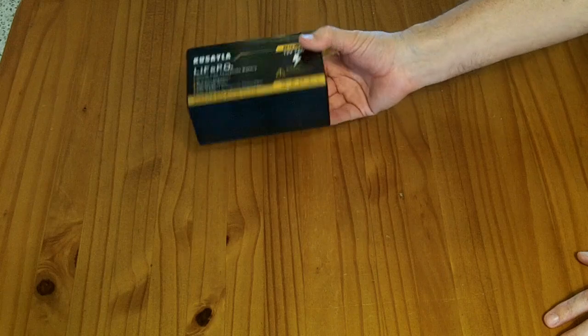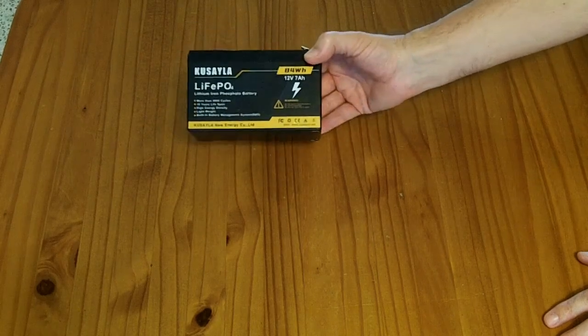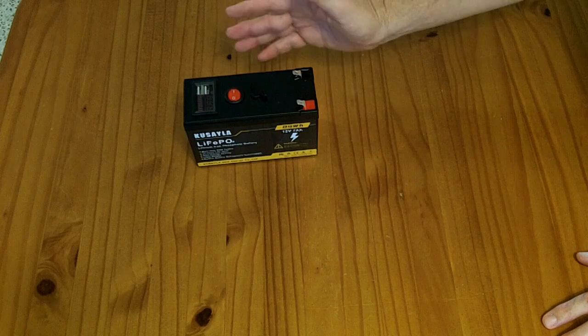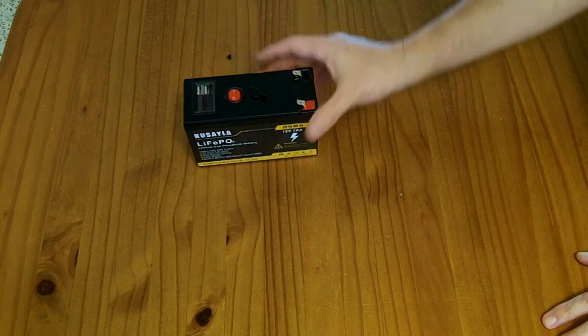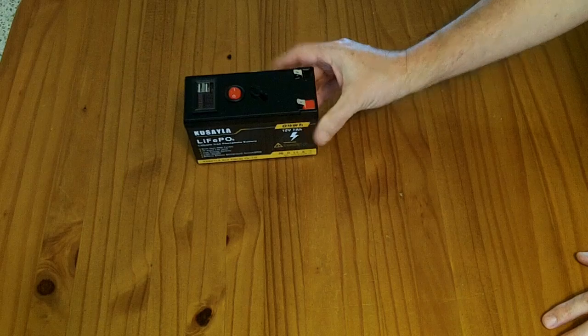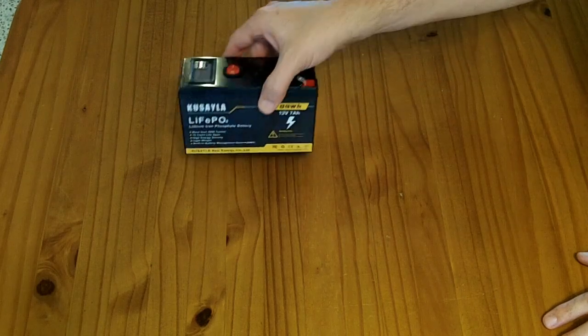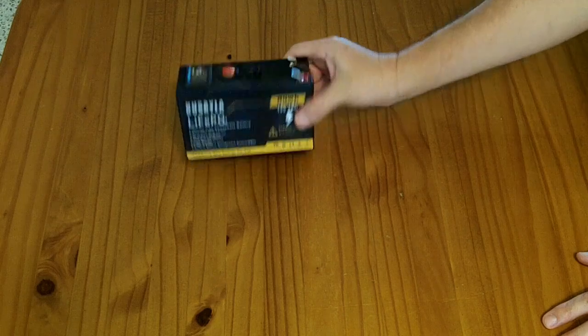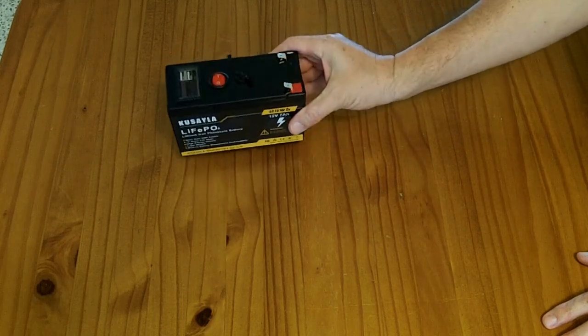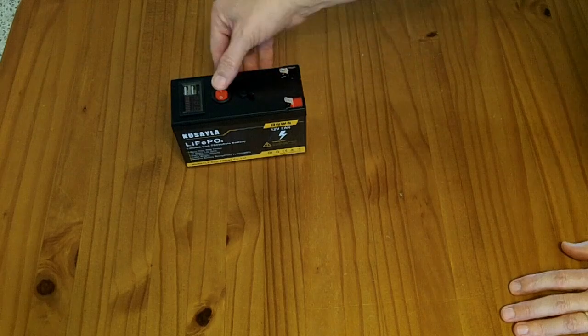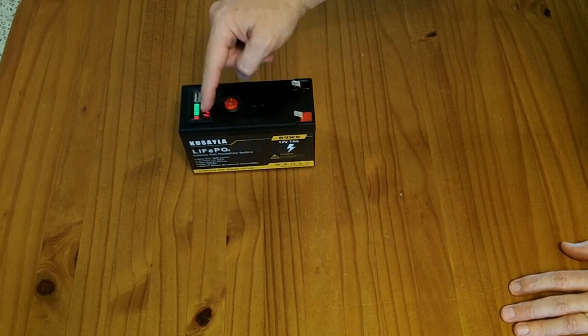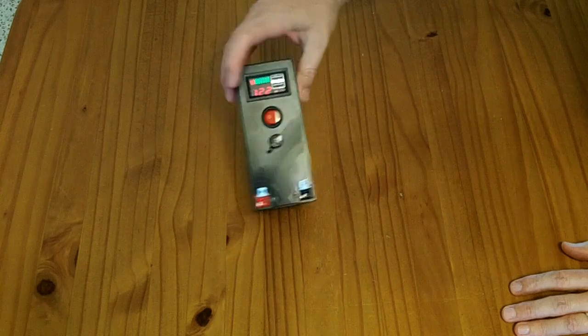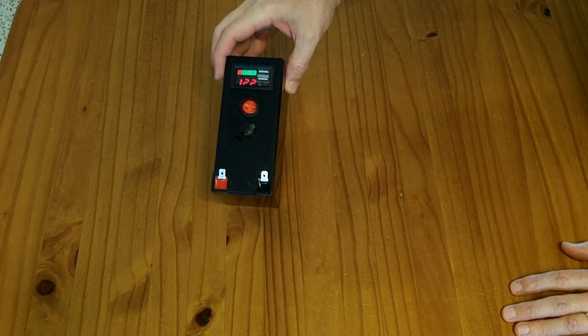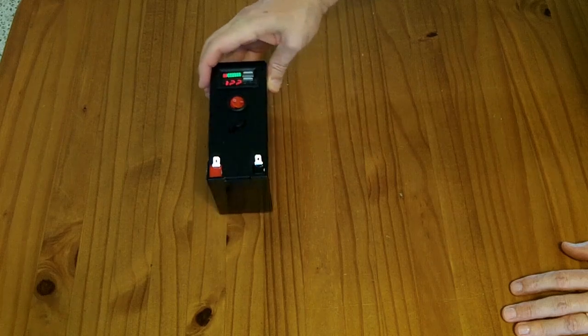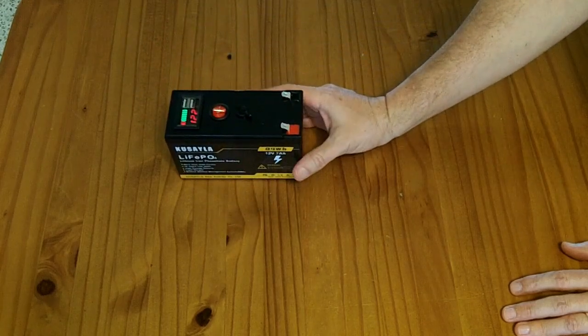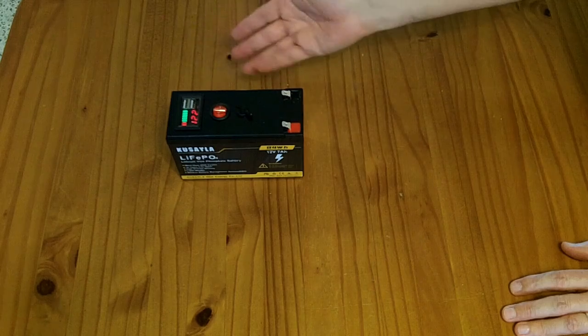So it appears to do what it claims to do and to meet its specifications. I'm a little hesitant to recommend this for unattended applications like a UPS system, just because with lithium-ion batteries there is always a small risk that it could burst into flames, more so than lead-acid batteries. I also don't know how much of a parasitic power loss this little meter and the USB circuitry here provides, so that's probably going to be more parasitic loss than you have on a lead-acid battery just sitting there.